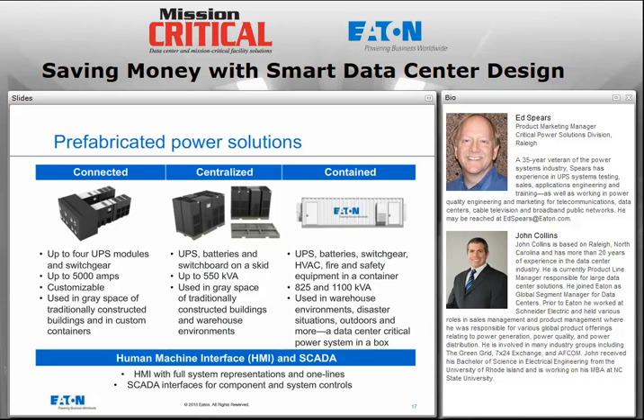The one on the left here is what we call our connected system, and you see that 2 large UPSs are actually bussed into the back of the switchgear in such a way that we do not have to deploy cable and conduit for the input and output and bypass for those 2 UPS systems. Between the UPSs and the switchgear, they literally plug in and bus together at the bus bar level, so it saves significantly on installation and deployment time.